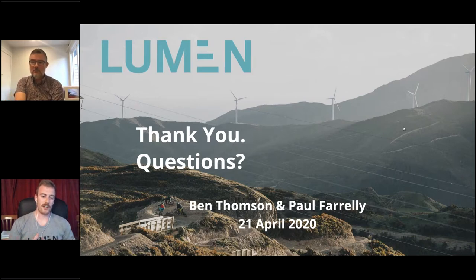Depending on what your capacity is, you might have enough capacity already, which would be really handy. If you don't have enough electrical capacity, talk to your network company. They'll be able to let you know how much it's going to cost to upgrade that capacity. It can be quite expensive depending on where it is. And then you need a Sparky to come around and look at your internals as well. Have you got the right size cables, the right size switch gear, all that sort of stuff. So that can be the real unknown in terms of costs. The heat pump itself, there's heaps of good manufacturers out there that can give you pricing on that.